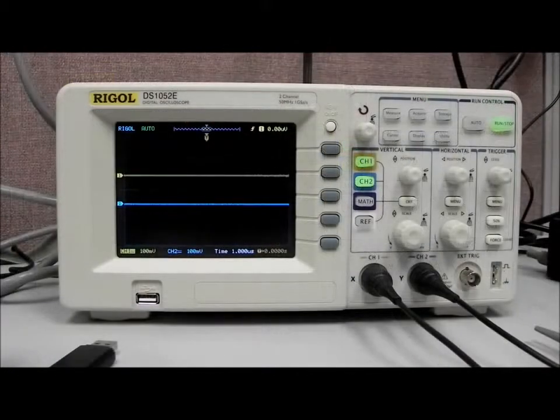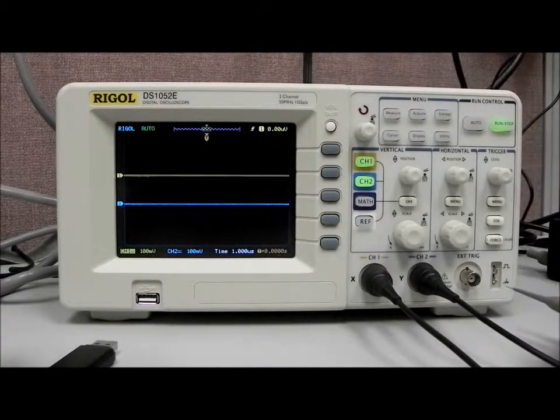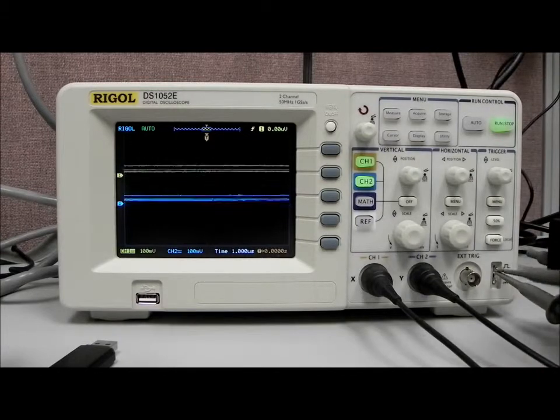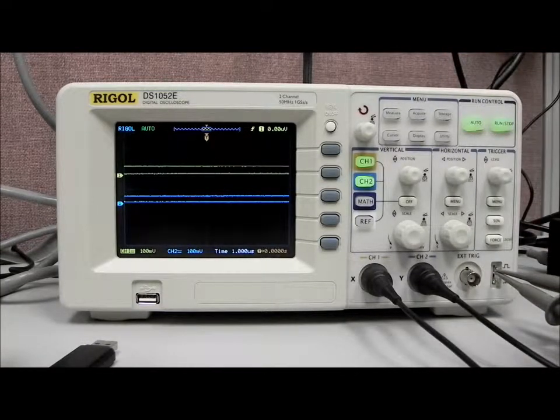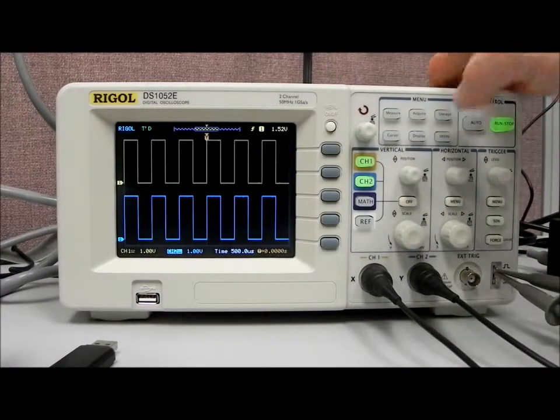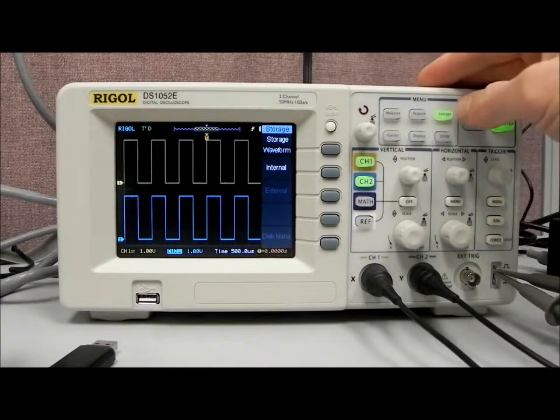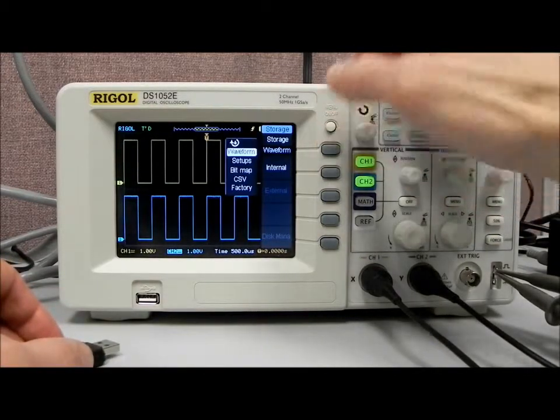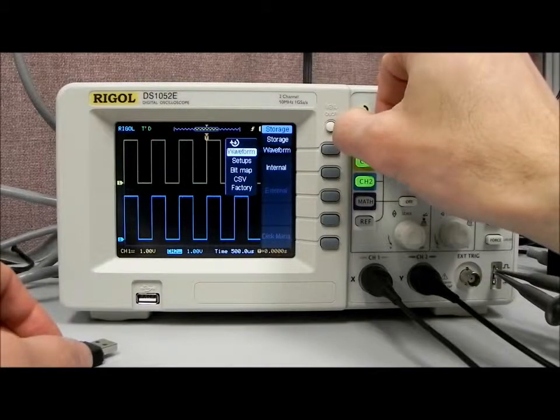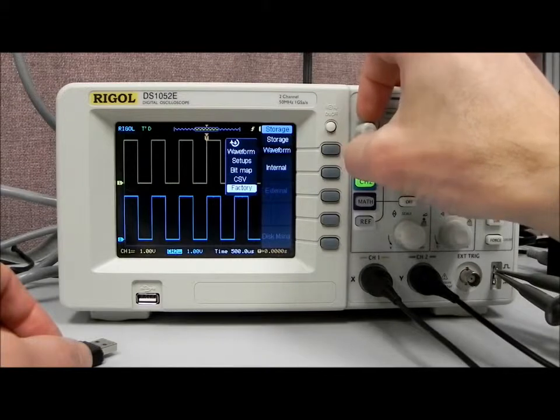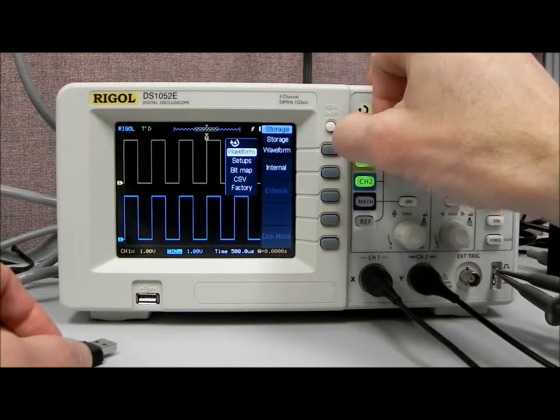I'd like to take a closer look at some of the storage capabilities of the DS 1000 series of scopes. I'm going to connect channel 1 and channel 2 to the square wave generator. I'm going to press auto, so now on this display we should see two square waves. Now let's say I wanted to store that particular waveform. I hit the storage key and now I have the storage menu.